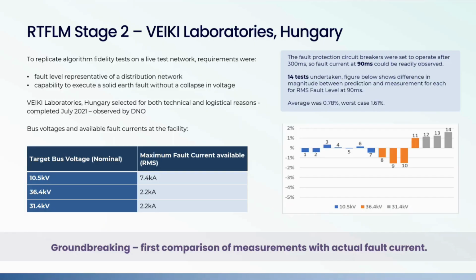So I think we've got the comparisons. So as you can see there, we captured 14 measurements where we directly compared the predicted fault level from the real-time fault level monitor with the fault current that was measured during those tests. And the difference in magnitude between the predicted measurements and the actual measurement for RMS fault level, the 90 millisecond RMS fault level, the average was around 0.78% with a worst case of 1.61%.